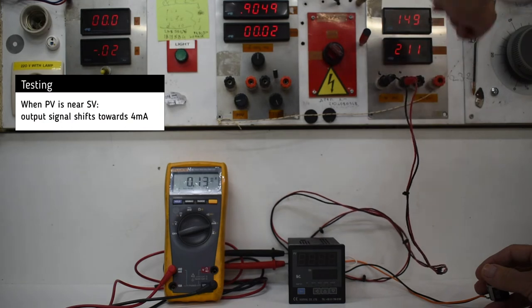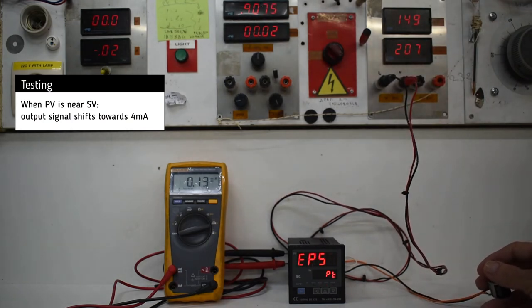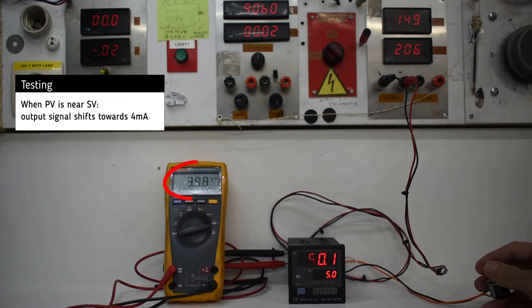As we near the set point by manipulating the input signal with a potentiometer, the mA output can be seen on the multimeter screen, and it's 4 mA.